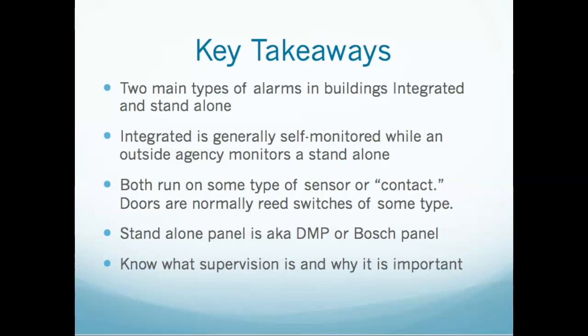Both run on some type of sensor or contact. Okay, doors are normally reed switches of some type, either the recessed type, the plunger type, or the surface-mounted type that I showed the pictures of. That's just a standard contact. It's very easy to install, and they're so simple that they tend not to break or break down on you. So that's what normally people use on doors.